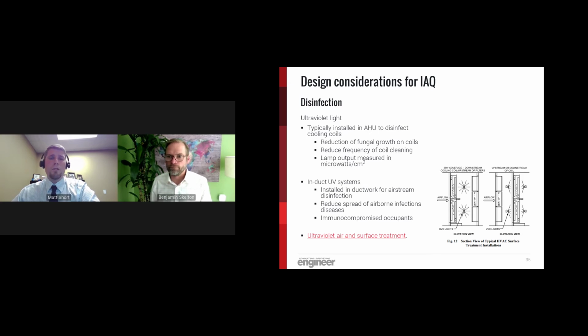Also listed here, which is a much less common application of UV light, is an in-duct installation. The intent for the UV light here is to disinfect the actual airstream. However, this is very rarely specified due to a variety of results on effectiveness.